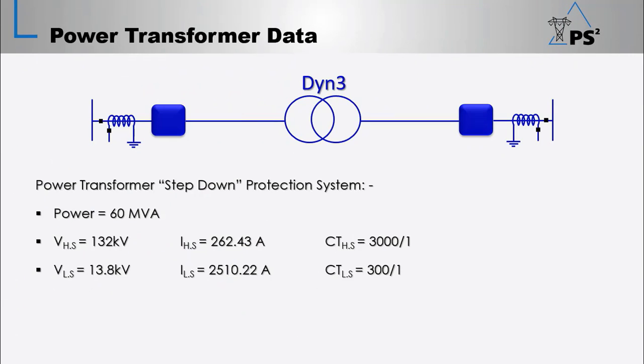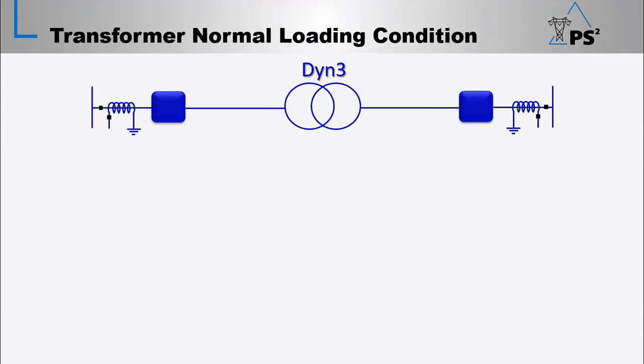Now we have a case study for a step-down power transformer with the following data, where the apparent power equals 60 megavolt ampere, the delta side voltage is 132 kV, while the star side voltage is 13.8 kV, the delta side rated current is 262.43 amps, while the star side rated current is 2510.22 amps. The CT ratio is 3000:1 for the delta side, while for the star side it is 300:1. During the normal loading conditions, the primary current flow through the power transformer would be in this direction. And with subtractive CT polarity, the secondary current flow through the CT secondary circuits would be in this direction.